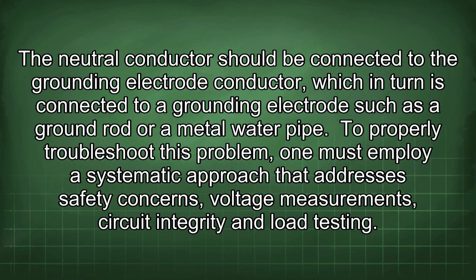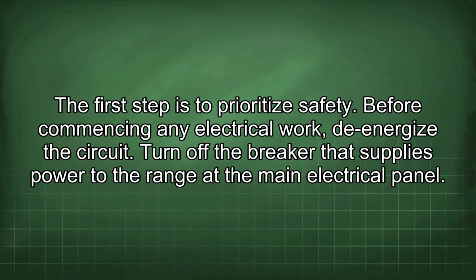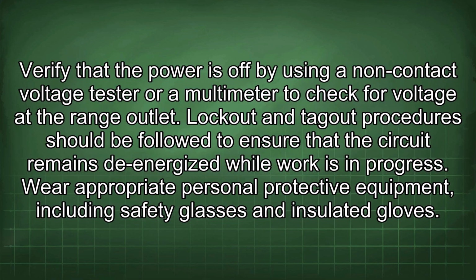To properly troubleshoot this problem, one must employ a systematic approach that addresses safety concerns, voltage measurements, circuit integrity, and load testing. The first step is to prioritize safety. Before commencing any electrical work, de-energize the circuit. Turn off the breaker that supplies power to the range at the main electrical panel. Verify that the power is off by using a non-contact voltage tester or multimeter to check for voltage at the range outlet. Lockout and tag-out procedures should be followed to ensure that the circuit remains de-energized while work is in progress. Wear appropriate personal protective equipment, including safety glasses and insulated gloves.